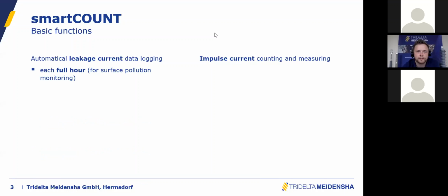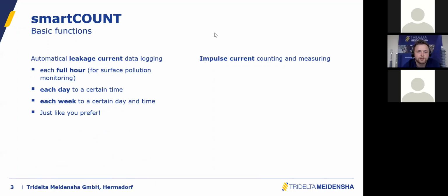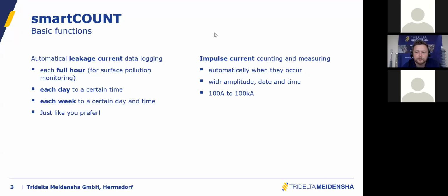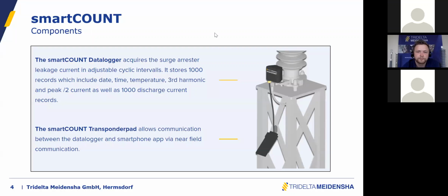For the leakage current data logging, we can log a full hour each day or each week, just like you prefer. This happens automatically and cyclically, so you don't have to care. The device does it by its own. And for the impulse current measuring, it happens, of course, also automatically when a discharge in the surge arrestor is taking place. And it will be recorded with the amplitude measurement, with the date and time, and in a range from 100 amps to 100 kiloamps, so a very wide range of current measurement.